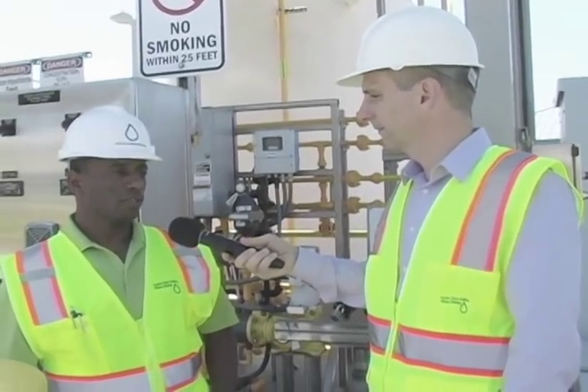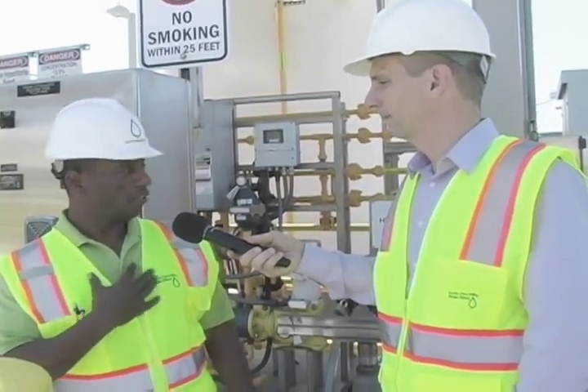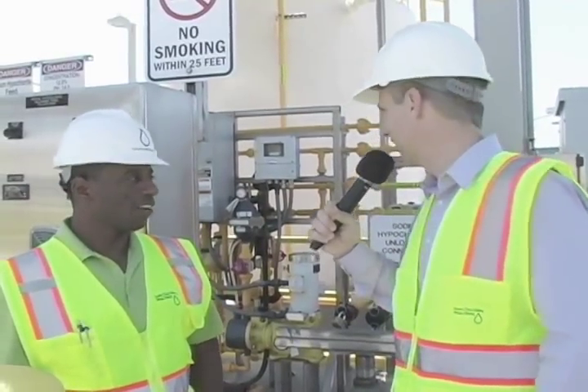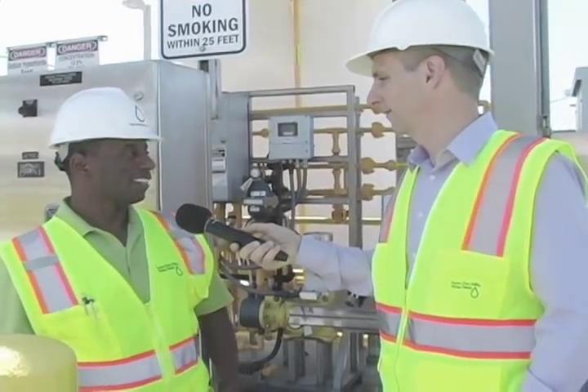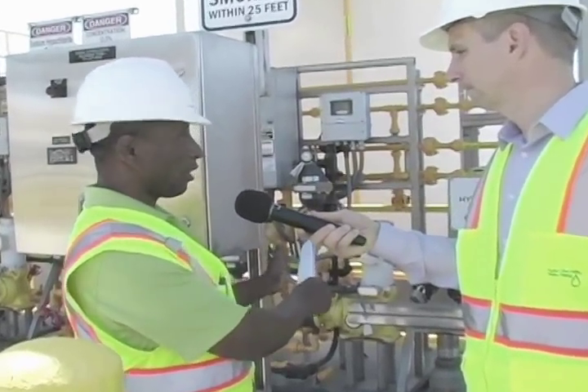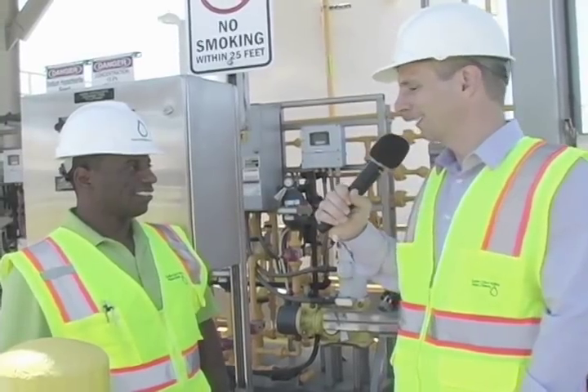For employees and visitors, we have a minimum of personal protective equipment required. As you can see, I'm wearing a hard hat, a vest, and we require goggles at least. The yellow markers are the barriers — once you cross that barrier you're supposed to be wearing goggles. Each of the tanks is also situated in a containment basin. In case the tanks rupture, that containment area is designed to hold 110% of the tank capacity, so even if a tank ruptures, all the chemical will stay contained and be disposed of accordingly.